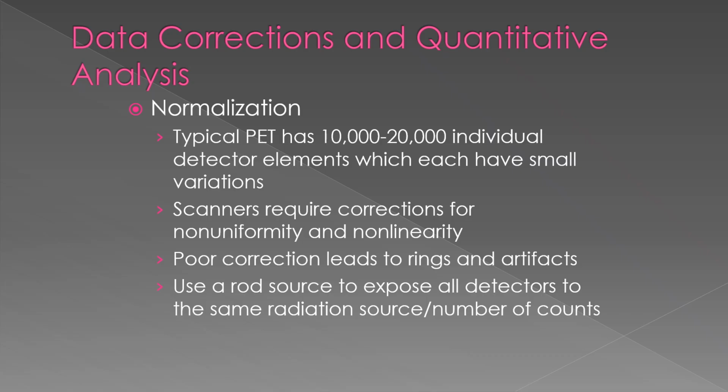Now, I want to talk to you guys a little bit about the QC. We're not going to talk about that until next week, but there's something that I want you guys to keep in mind. With the regular gamma camera, when we talked about QC, most things are QC checks. The daily uniformity is a check. The weekly bar phantom is a check. The Jaszczak phantom, that's a check. Even pixel size, that's a check.